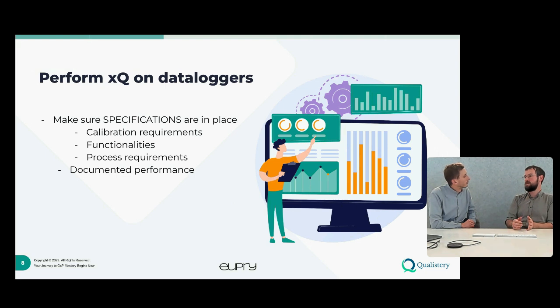We see a lot of our customers not having clearly defined requirements. So the top ones at least are, first of all, what are the calibration requirements? I think this is in some cases our own fault as calibration providers. We've been too good at suggesting calibration points that are typically used in industry, but it's very important for you and your organization to have defined your specifications and requirements for calibration. What is the maximum permissible error? What calibration points do we need, and what are the rationales behind them? Because those are really important to be able to justify to an auditor.